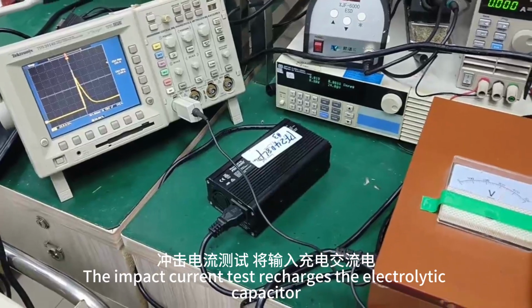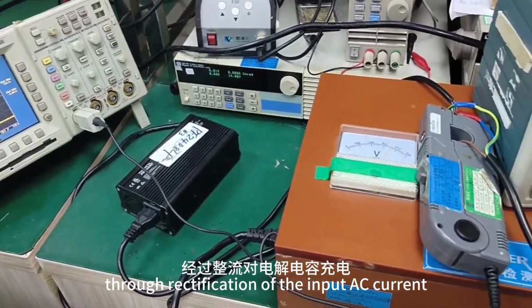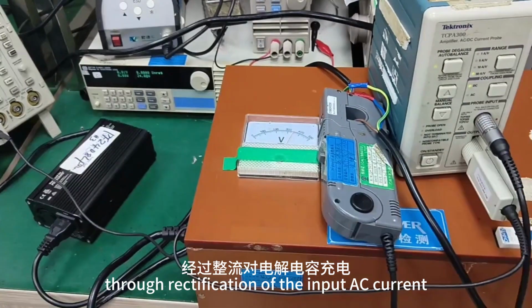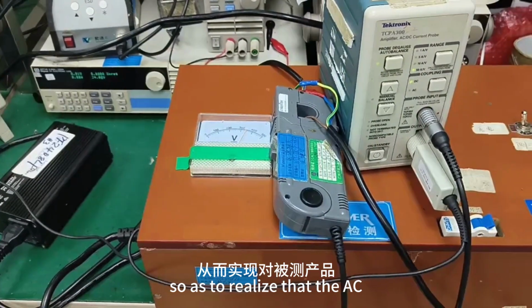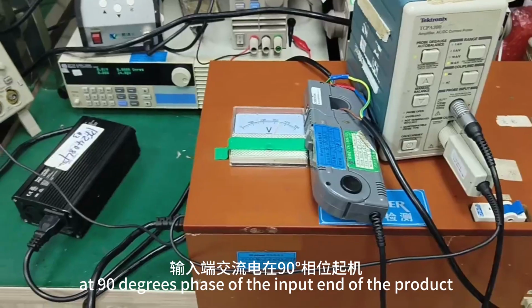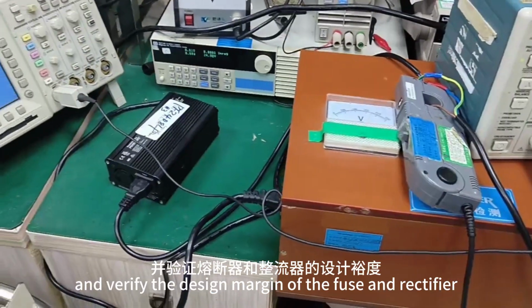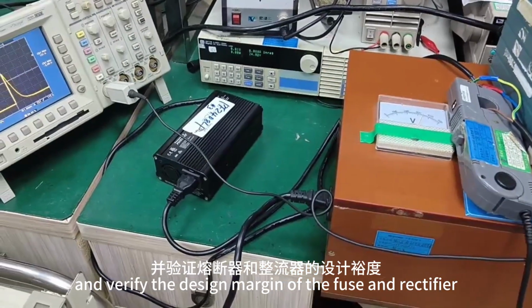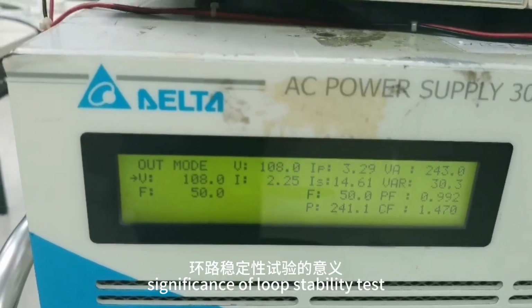The impact current test recharges the electrolytic capacitor through rectification of the input AC current, so as to realize the AC at 90 degrees phase of the input end of the product under test, and verify the design margin of the fuse and rectifier. Significance of loop stability test.